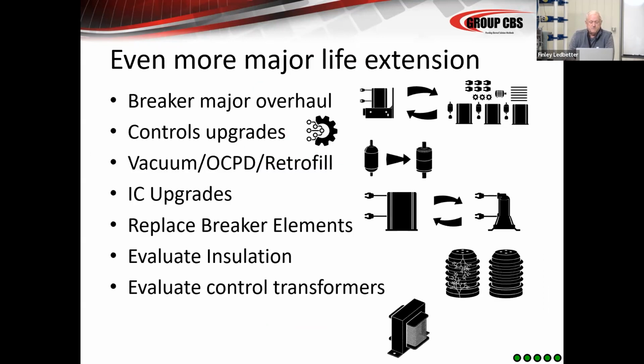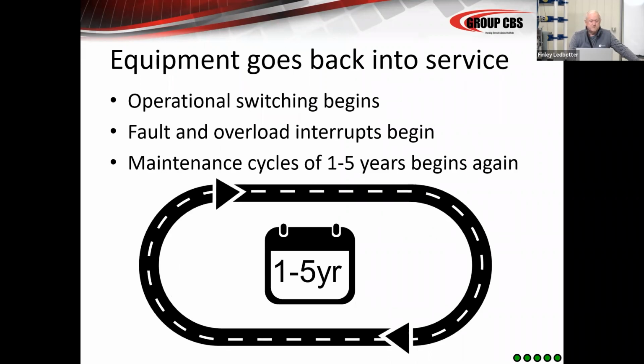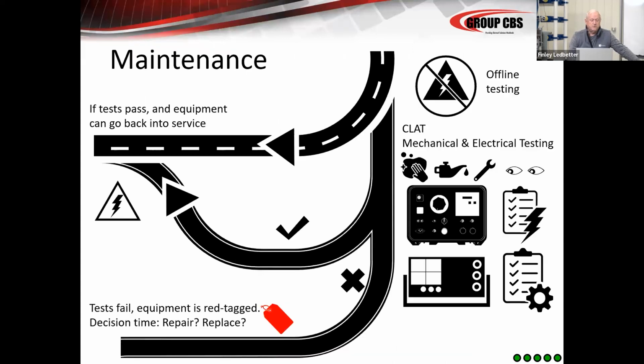Even more major life extension, major breaker overhauls. We're replacing controls. We're retrofilling them with new breakers. We're installing new breakers in the place of the old ones. We're keeping the switchgear so we don't have to disturb the cables. We're completely replacing the breaker elements. We're upgrading the IC. We're evaluating the insulation. We're evaluating control transformers and replacing transformers. We're finding a lot of insulation breakdown in insulators and different types of insulation. And a lot of that can be picked up pretty easily with online techniques and non-destructive testing. It goes in for another 5, 10, 15, 25. It comes out now, it's 100 years old.